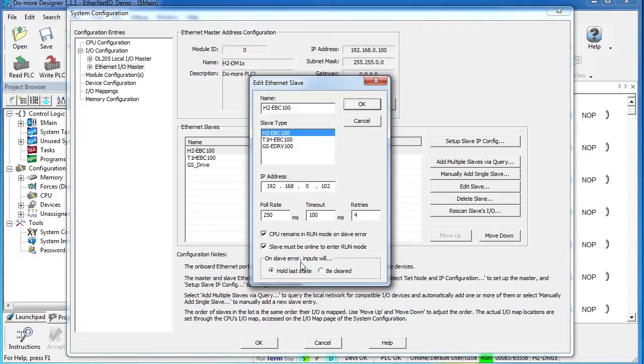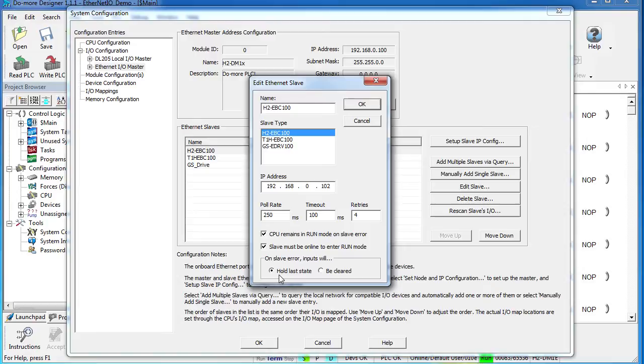One nice feature I like is that when the slave has an error, what do you want its inputs to do? Me, I like for them to hold their last state so that I can see exactly what the system was seeing when things crashed.